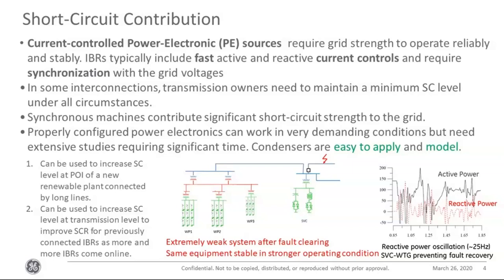That helps improve the grid strength. And this grid strength helps not only in reliable operation of the IBRs, but it also helps in proper operation of your protective elements. It also helps arrest some of the transient overvoltages on fault clearing, on switching events, and transients, right?